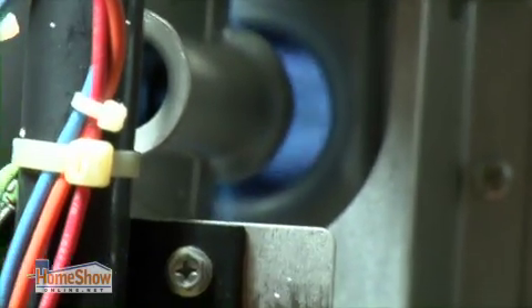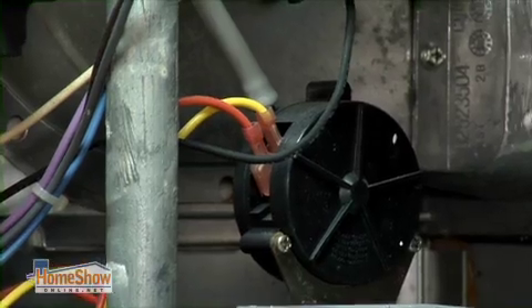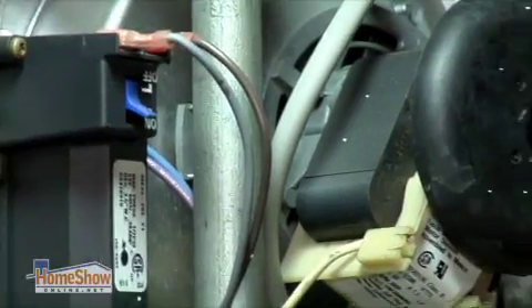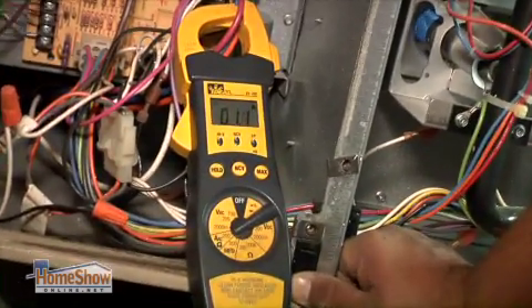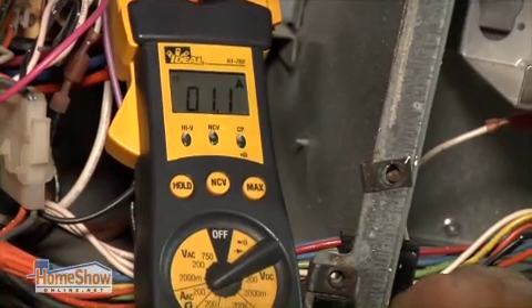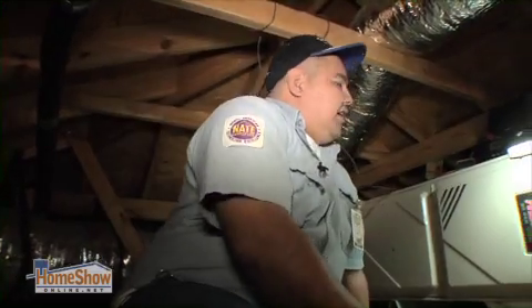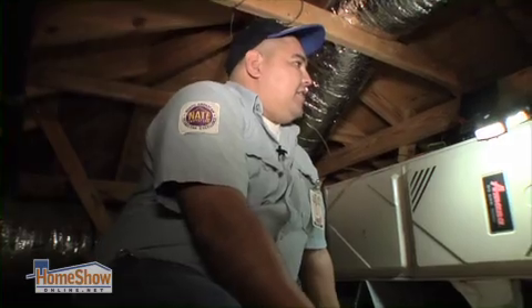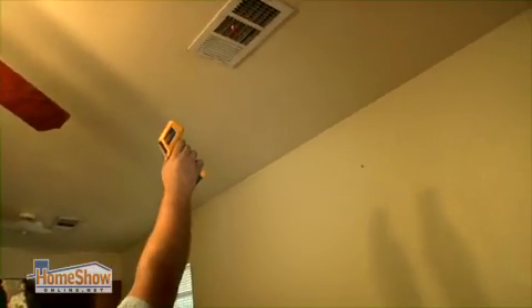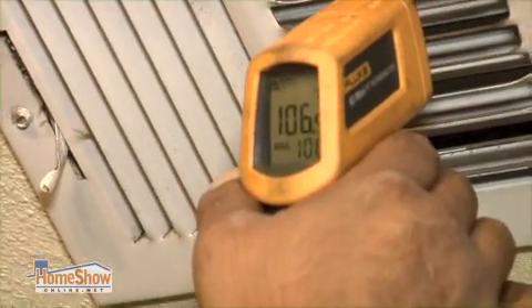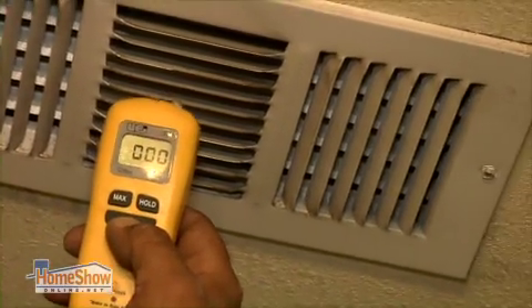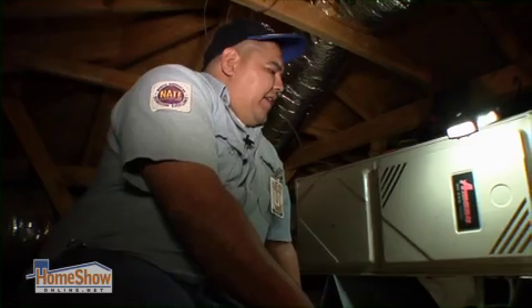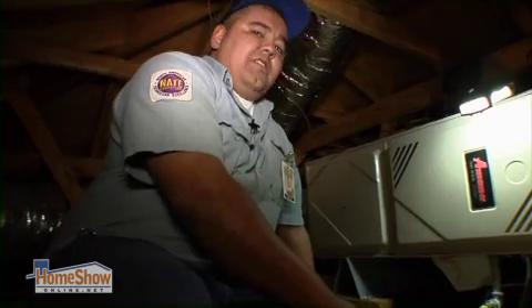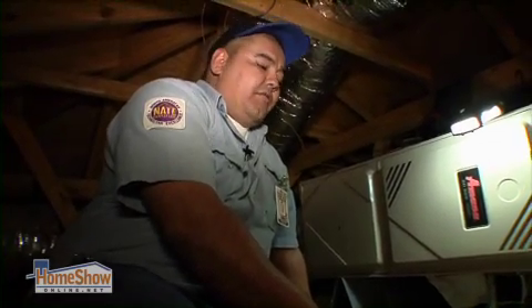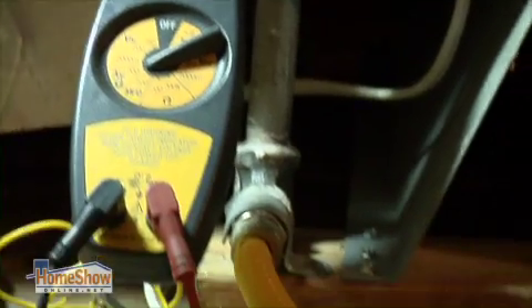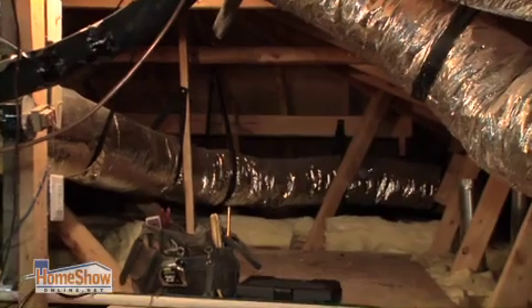I check the ignition of the furnace, as well as the amps and the volts of the blower motor and the inducer motor. I also check the ohms in the hot surface igniter, make sure that's not weak. Check the static pressure across the system. I'll check the temperature differential, which is the temperature in the supply and in return, the carbon monoxide level, combustion, and I'll make sure the furnace is tuned up and operating safely for you and efficiently. All the components need to be working properly to maintain comfort and safety.